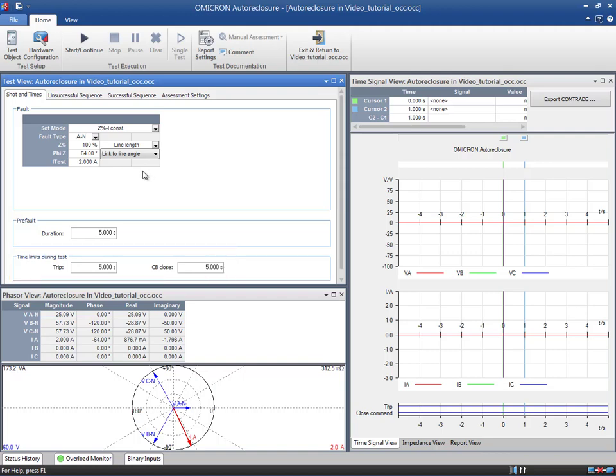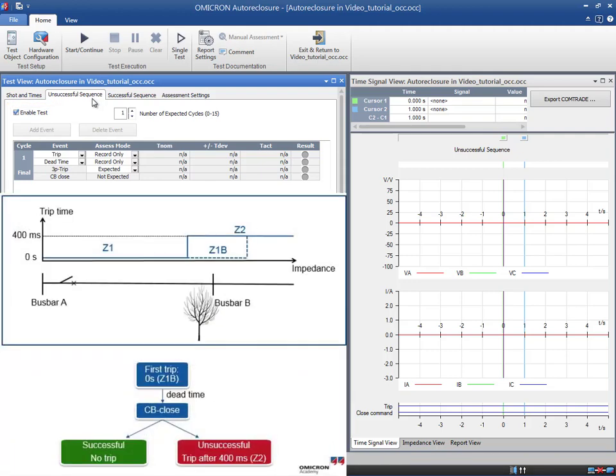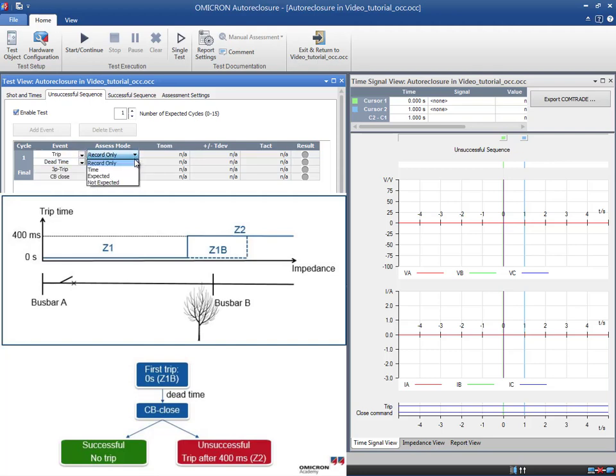The next tabs are the Unsuccessful Sequence and the Successful Sequence. These two tests are connected — it is only necessary to configure the test in the Unsuccessful Sequence tab and the information is then captured into the Successful Sequence tab. If you are not interested in performing either of these two tests, just clear the box to disable it. The drop-down menu in the first column presents a list of possible events to be measured. In our case, the first event will be the Trip. Regarding the Assess Mode, we take the Time option. This way, we can enter the nominal expected time and the tolerances specified in the manual for an automatic assessment of the results. It is also possible to simply record the signal or to check whether the signal is detected or not.